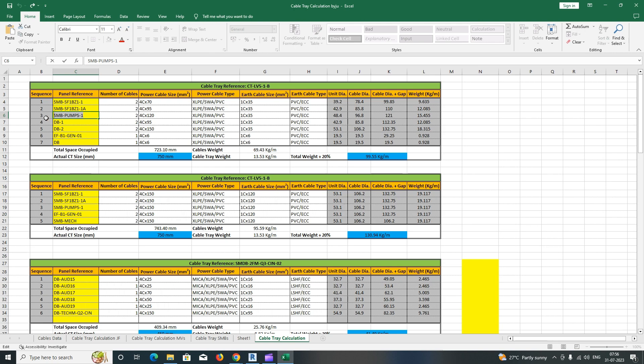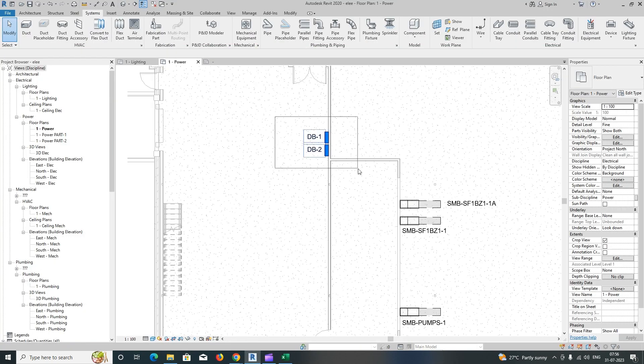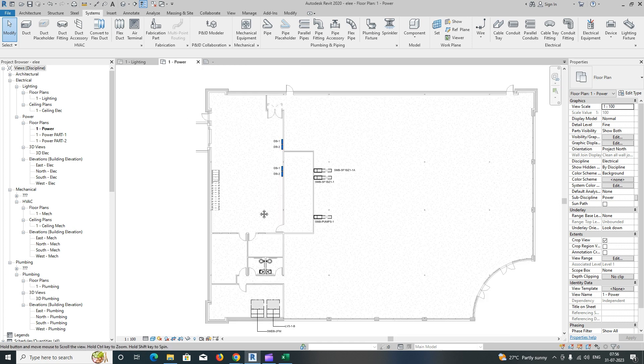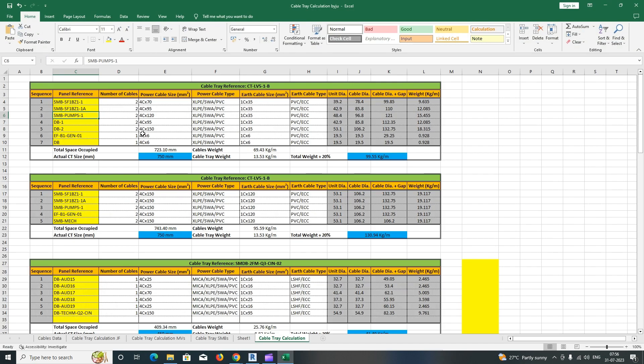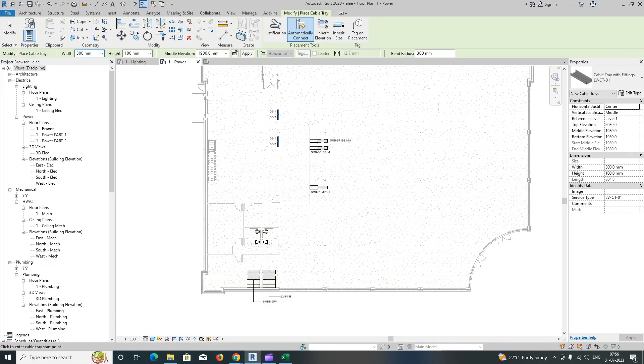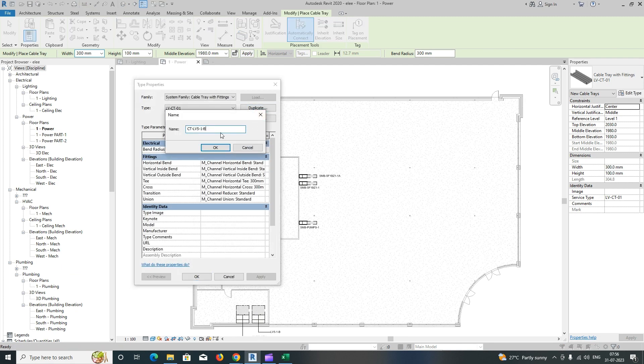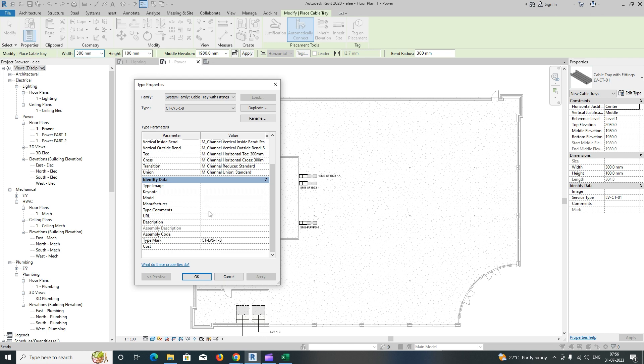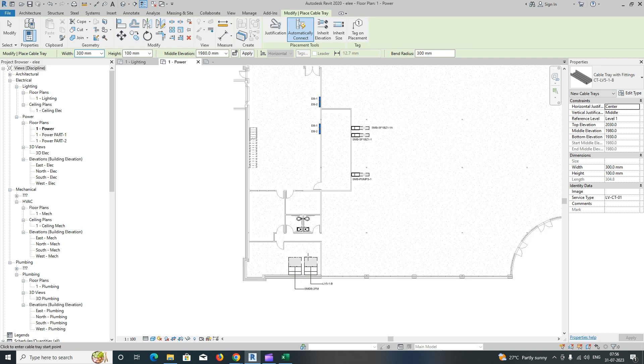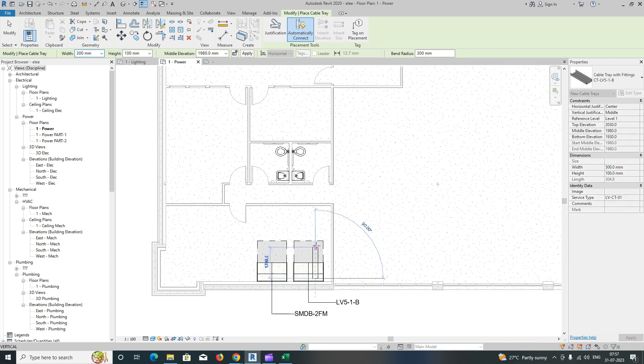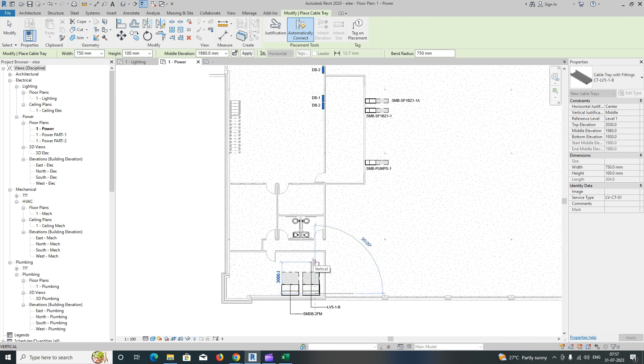Now that's fixed. There are some others too, but I'm not considering them now. You can copy them and place them as per your schedules. This cable tray is coming from this panel, so we need to find the perfect route. I'll go to cable reference, copy and duplicate it, and give the cable reference name and type mark. You can also add descriptions in the comments. Then we'll draw the cable tray starting from this panel - the required size is 750mm.